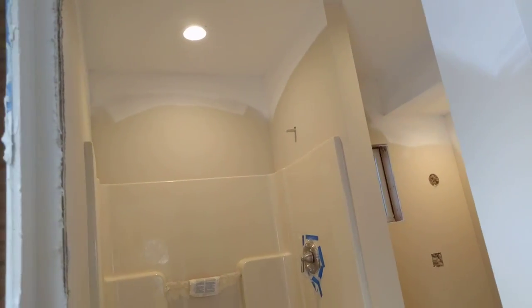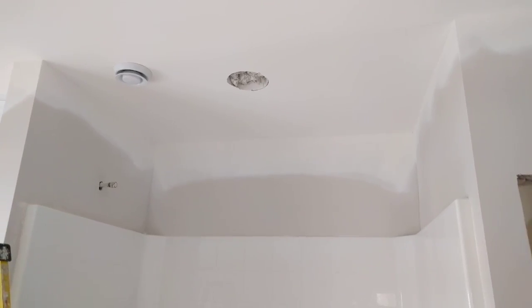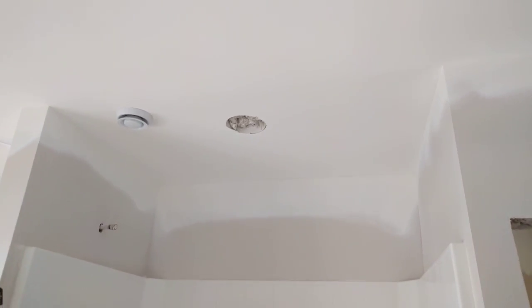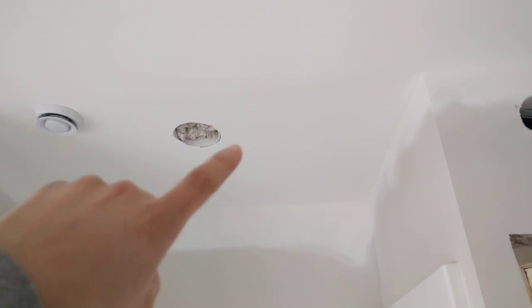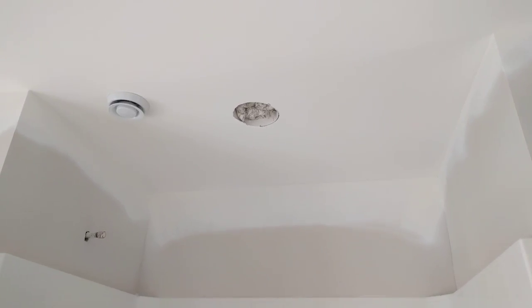Basically the requirements for a light above the shower are that the light can't be dangling down, and it has to be rated for wet locations. Here's a light that's above a tub shower — same situation except the trim kit has not yet been installed. This is a 6-inch recessed lighting fixture, and that's what I'm going to recommend: get a 6-inch or 5-inch recessed light fixture to install above your tub shower or shower.